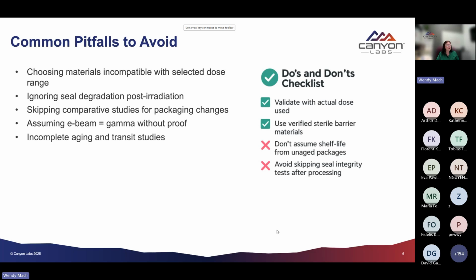The second thing to think about is ignoring seal degradation post-irradiation. Even if your packaging seals are properly validated before sterilization, radiation can weaken or distort these seal layers, especially, like I mentioned, in multi-layer film. So understanding seal integrity before and after dose exposure is critical. What is a statistical difference? And making sure that you set your acceptance criteria appropriately. Skipping comparative studies: if you switch from gamma to E-beam or potentially adjust dose ranges to widen the range, don't assume that your packaging will behave the same. Subtle changes in modalities could cause performance differences, and they should be validated or justified.